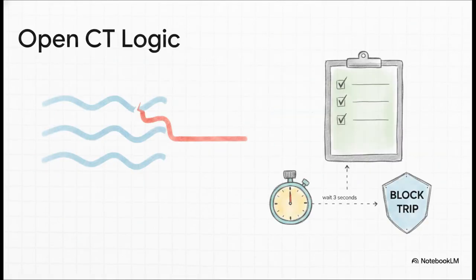Okay, so once that 10% threshold is met, the relay runs through a rapid-fire checklist. It notices one phase drop to 0. But then it checks the other phases. Did their current spike like it would in a real fault? Nope, they stayed perfectly identical. Are there any 0 or negative sequence fault currents present? No. By verifying these highly specific clues, the relay confidently deduces that, hey, a wire is merely broken. It waits precisely 3 seconds, issues an open CT alarm, and blocks the differential trip. Boom. A simple broken wire doesn't cause a citywide blackout.